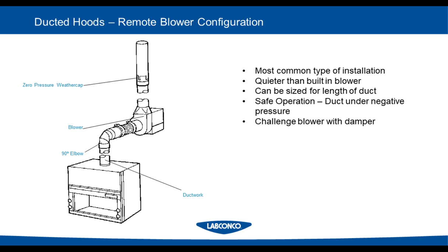Next, you can also challenge the blower with a damper. This typically goes between the fume hood and the blower, and that allows the system to be balanced more easily and ensures that the blower is operating within its most optimal range.